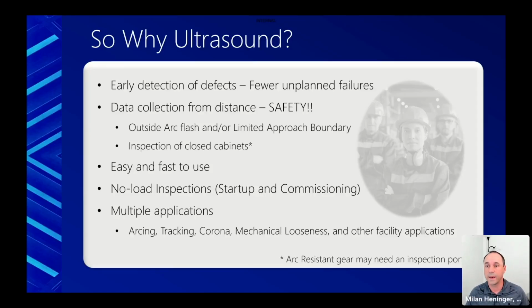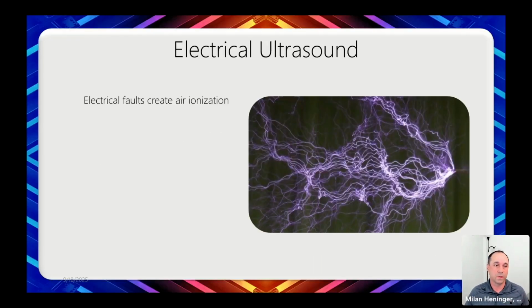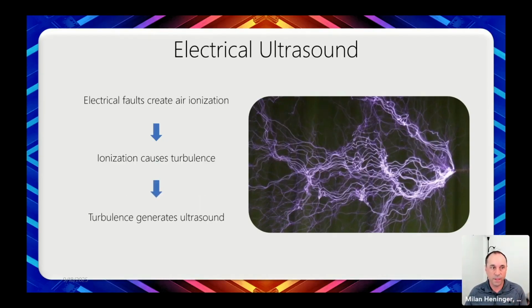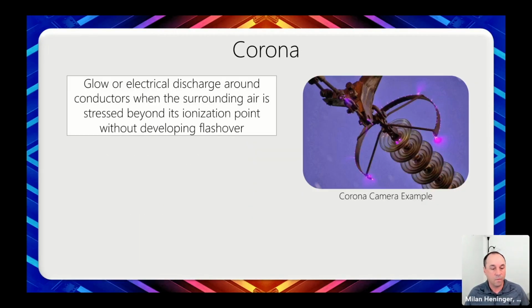So I want to give everybody kind of an overview of electrical ultrasound and how this works. So in most of your partial discharge, those electrical faults create ionization of the air. That ionization creates turbulence, which is able to be detected by ultrasound. All right, so we're picking this up airborne via the turbulence that's created by ionization. And one of the main forms that we see, especially on your high voltage systems, is going to be corona.